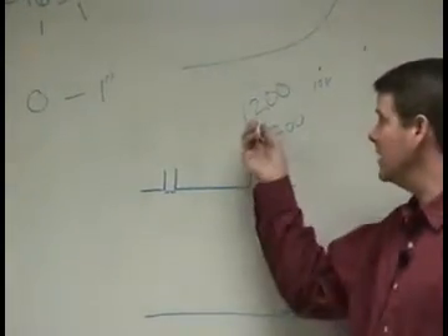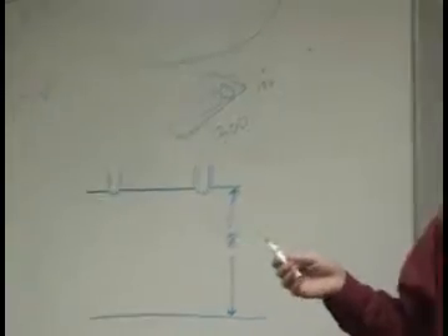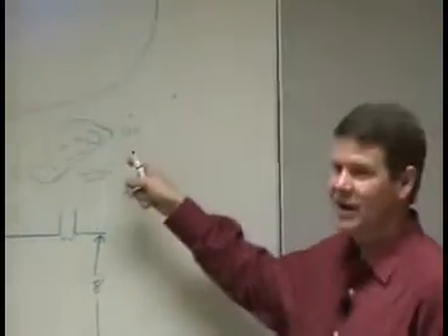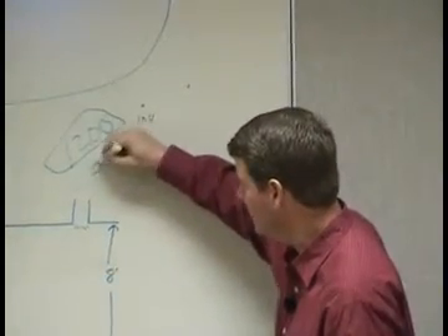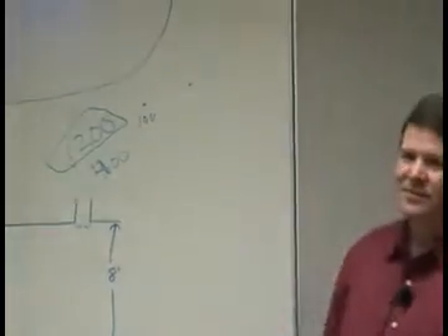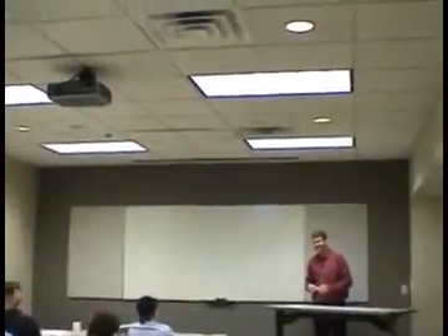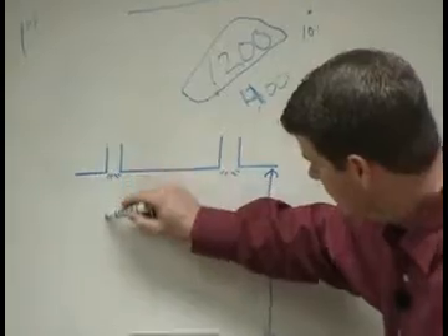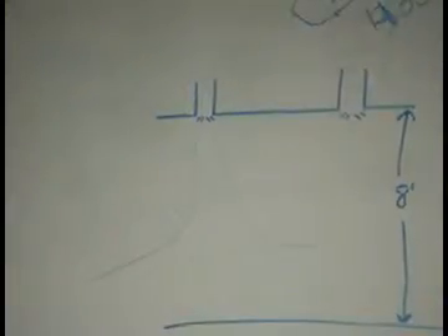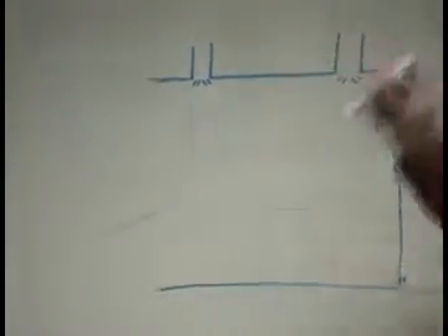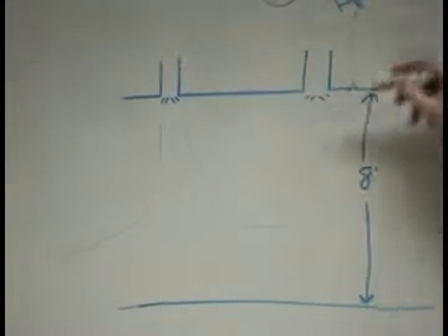Now that's at 1200 CFM. But we don't have 1200 CFM. We've got 300, 400 CFM. Let's say our minimum is 400. We got 400 CFM coming out of 4 registers. Now if you stuck your hand up to that register and tried to feel 100 CFM, how do you think you'd do? You're going to feel hardly anything. It's going to be trickling out of there. So what does that do? When we had 300 coming out, we had some pretty good throw getting it down there. And of course it was cold air too, so throwing cold air down is a lot easier. It's like throwing with the wind.